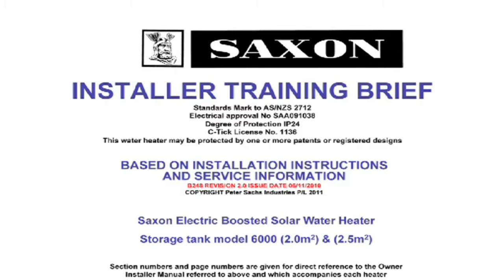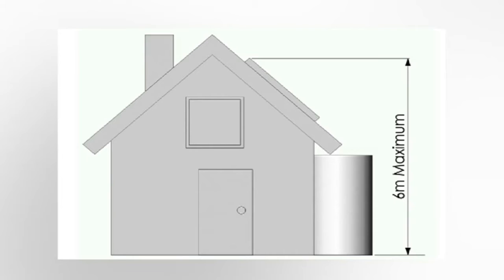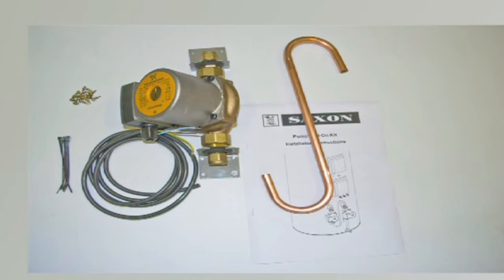The brief is not meant to replace the full written instructions in the owner and installer manual. The pump provided is good for up to 6 meters from the ground to the top of the panels. Otherwise, order the booster pump for a 12 meter lift.